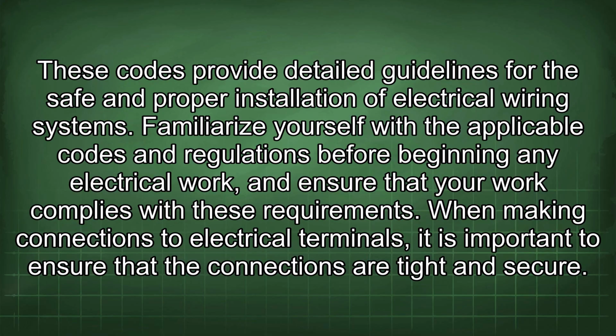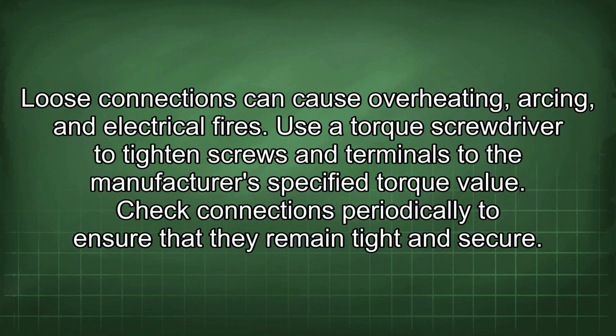these requirements. When making connections to electrical terminals, it is important to ensure that the connections are tight and secure. Loose connections can cause overheating, arcing, and electrical fires. Use a torque screwdriver to tighten screws and terminals to the manufacturer's specified torque value. Check connections periodically to ensure that they remain tight and secure.